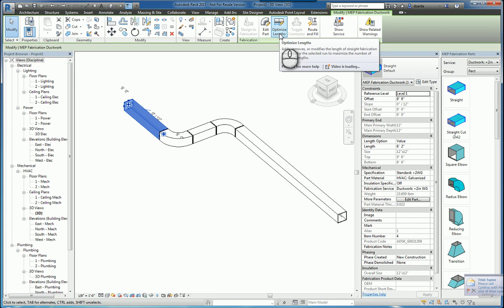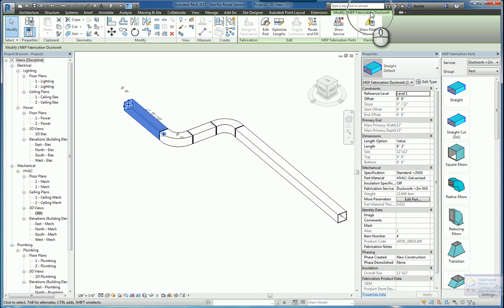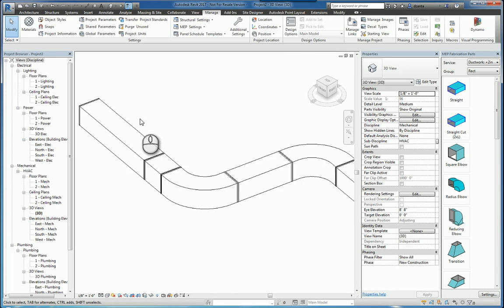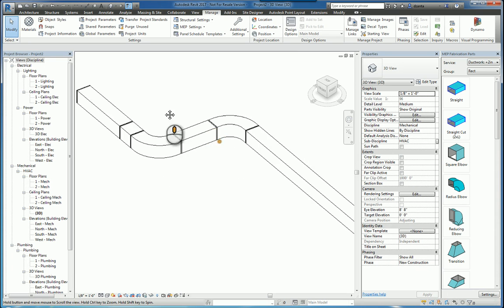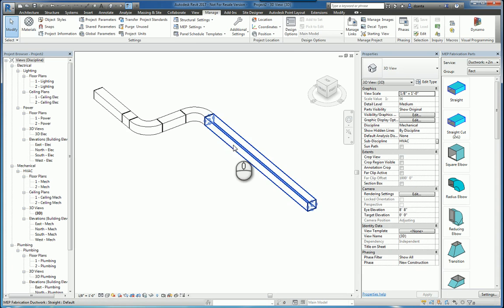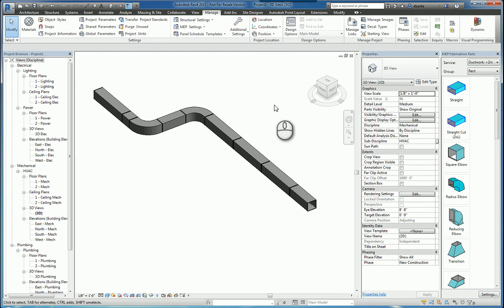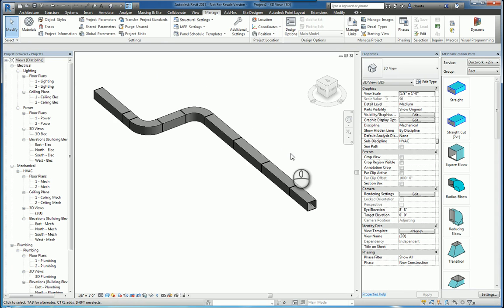I can also select it and click Optimize Length in the Modify MEP Fabrication tab. If I click Optimize Length, it'll put in that 4'11" — really a 5' long segment — and then put in a connecting piece for the remaining length. You can very quickly use Revit fabrication tools to build a fabrication-based ductwork with those parts that are available.